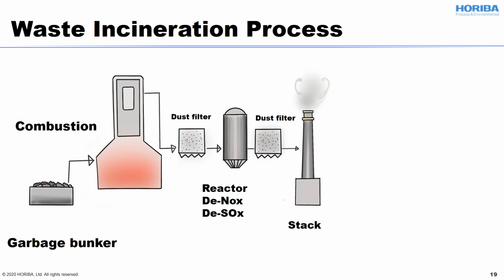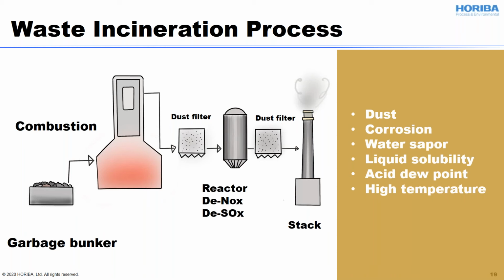For the emission gas analyzer, the waste incinerator process gas is well known as containing high dust and highly corrosive gas, and it contains rich water vapor, liquid solubility, an acid dew point, and high temperature. Those are the features of the gas from the incineration. The analyzer is required to be durable enough for those sample gas measurements, and the sample handling system needs to be well built to deal with those gases.